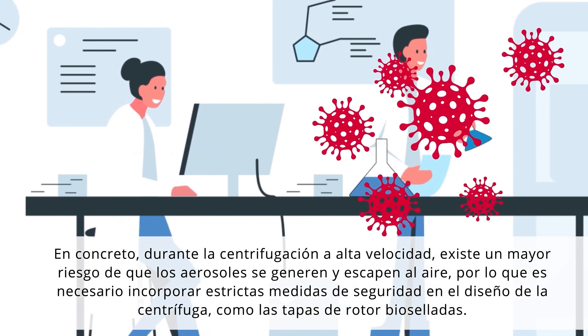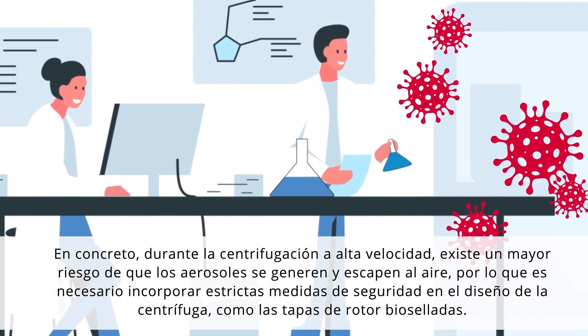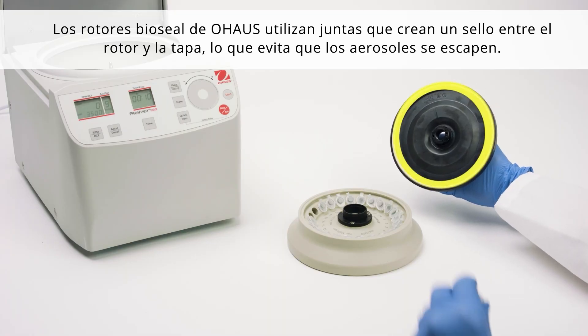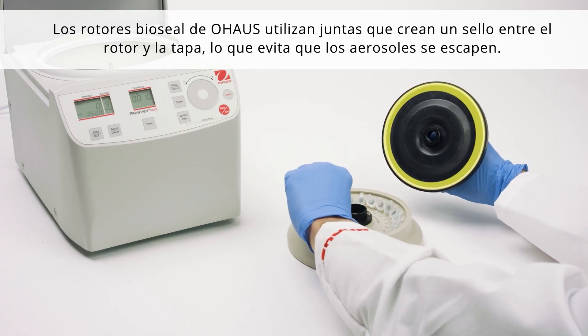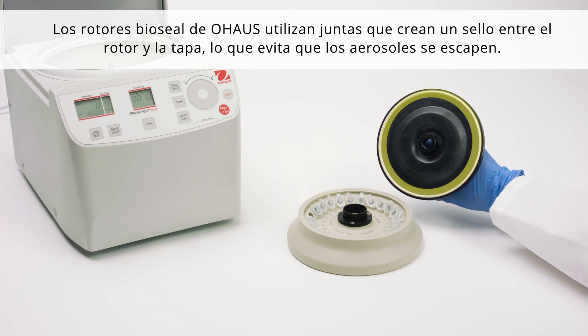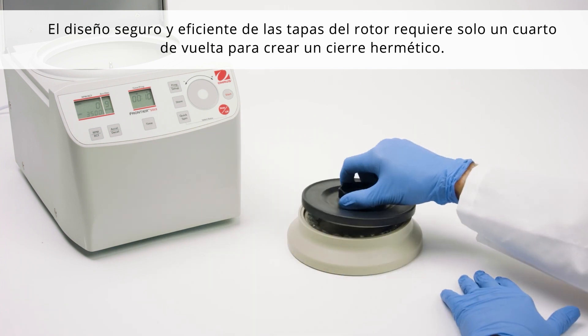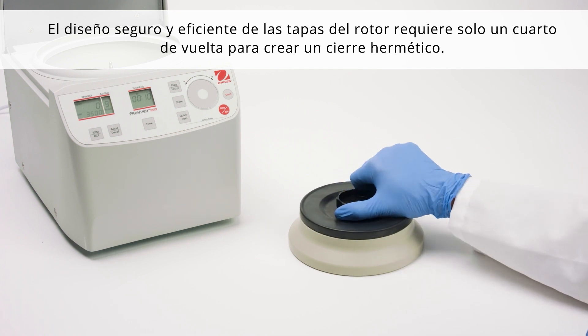Therefore, strict safeguards need to be built into the centrifuge design, such as bio-sealed rotor lids. OHAUS BioSeal rotors use gaskets that create a seal between the rotor and lid, preventing aerosols from escaping. The safe and efficient design of the rotor lids requires only a quarter of a turn to create an airtight lock.